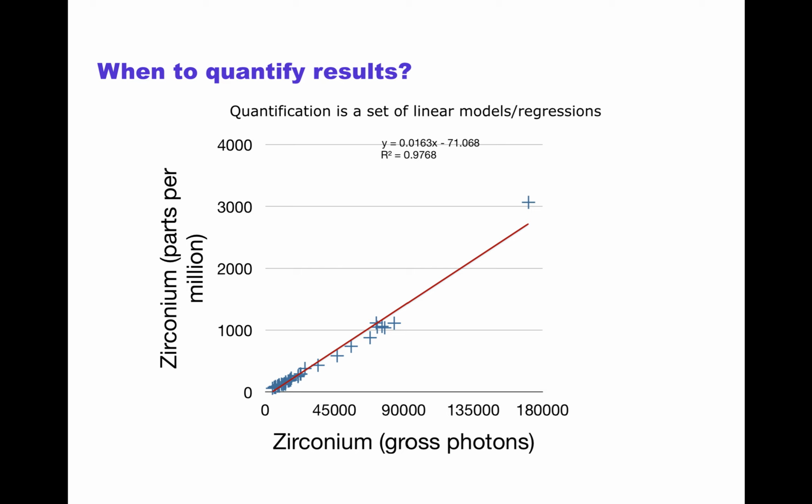This would introduce systematic error, which, while it could be corrected via another parameter, it would be better to tailor the data a little bit better. So in this case, we could remove that far data point and limit our line to get a better calibration. But sometimes we don't want to do that. We'd rather accept a higher variance rate. Why is that? Well, it comes down to statistical validity. While that high outlier point adds significantly more error in the accuracy, it does nonetheless still result in a valid concentration, provided we express that uncertainty.